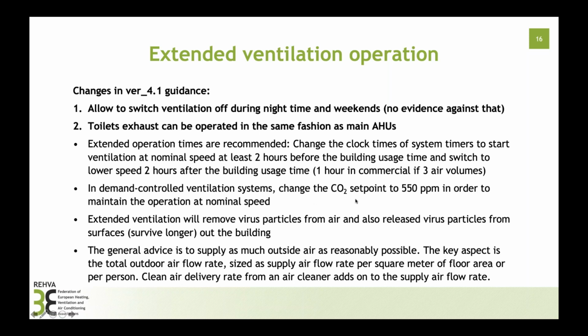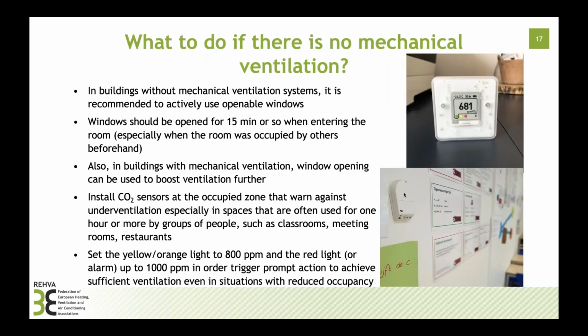So for demand control systems, it's recommended to change the set point to 550 ppm, with the thinking that outdoor concentration in large cities can be close to 500, and when you have a 50 ppm accuracy of this sensor, so that's the background of that 550 value. Well, and indeed there are many buildings where there are no mechanical ventilation systems, and especially in the winter time, it is indeed a big problem, because it's not so easy and not so comfortable to ventilate through the windows, but basically there are many recommendations on how to use this window ventilation for long enough periods, and when to use CO2 sensors, to use these as ventilation indicators.